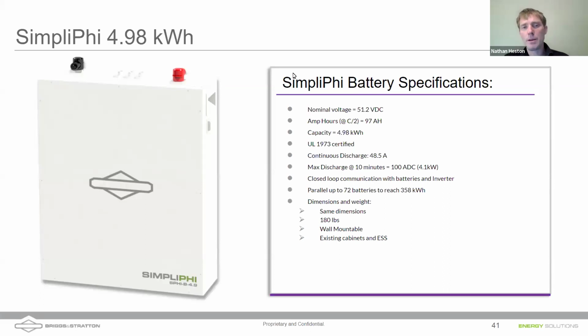This is an outdoor rated battery. The big difference between this and the other battery is the NEMA 3R enclosure, so you've got a battery that's waterproofed. A nice feature of this battery is that the terminals are offset, so you can run big 4-aught cabling straight across from one battery to the next when they're in line on a wall.